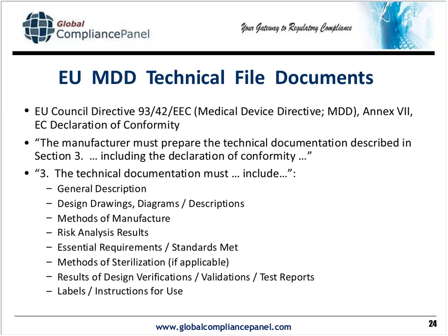Now, what you include in your technical file, again, this is spelled out in the Medical Device Directive, Annex, as I mentioned here, 7, and your declaration of conformity, which if it's a Class 1, you can do yourself. If it's a Class 2 on, you do it in harmony with your notified body, who reviews it and audits it. They audit your quality management system, which is a given. Under 13485, you have to have that.